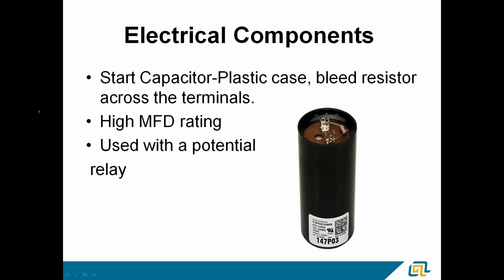Start capacitor, I get a lot of calls on these. Start capacitor has a black plastic case. There's a bleed resistor across the 2 terminals. And the function of that is to keep the capacitor from being out of phase with the incoming power. This way, when the capacitor gets power, it's in a neutral state and it'll respond better. It won't spark windings. They have a high microfarad rating. 122 to 145 is very common. And it's a range. It isn't just one single rating. It's a range. Use it with a potential relay.